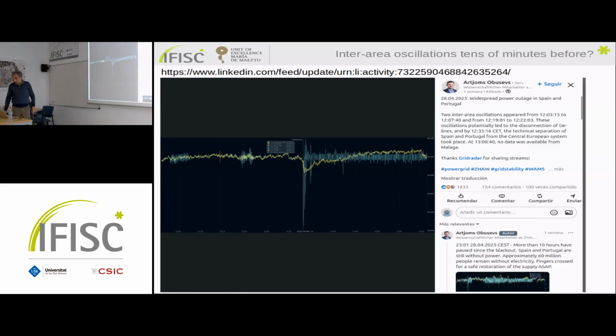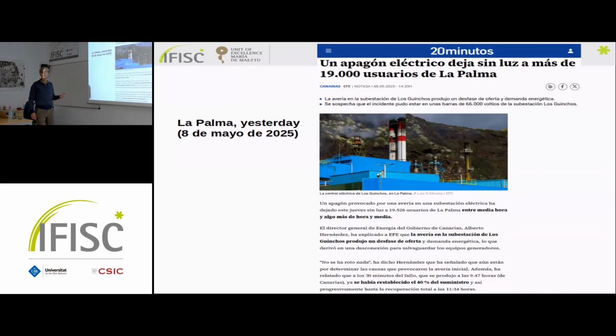This is in this block, and I'm not going to give you firm conclusions, just tell you something I think is sort of a conclusion: you might not be aware, but a couple of days ago, on May 8th, there was a blackout in La Palma. One substation got disconnected—the switchgear, the 'Guinchos'—and the fall of that substation introduced an imbalance between demand and generation, which led to the disconnection of several pieces of equipment to protect themselves, and that triggered a big blackout. Again, whatever happened in Spain happened in another way—something happens, and then a cascade of events follows. And with that, I finish.